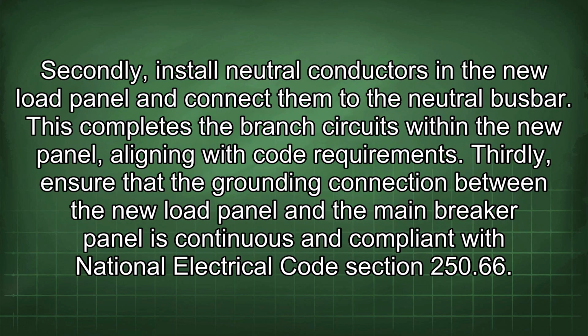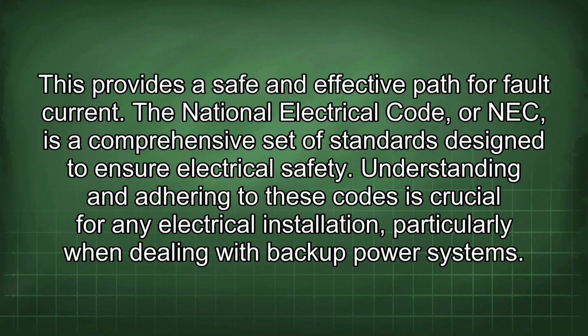Secondly, install neutral conductors in the new load panel and connect them to the neutral bus bar. This completes the branch circuits within the new panel, aligning with code requirements. Thirdly, ensure that the grounding connection between the new load panel and the main breaker panel is continuous and compliant with National Electrical Code Section 250.66. This provides a safe and effective path for fault current. The National Electrical Code, or NEC, is a comprehensive set of standards designed to ensure electrical safety. Understanding and adhering to these codes is crucial for any electrical installation, particularly when dealing with backup power systems.